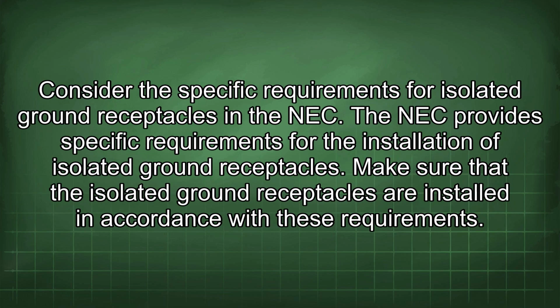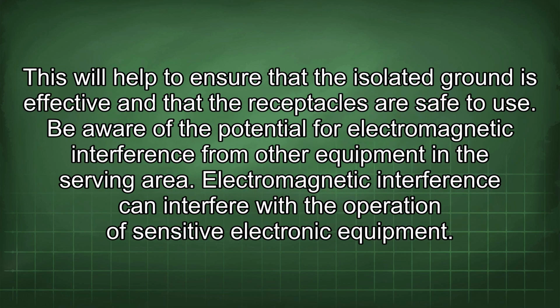Consider the specific requirements for isolated ground receptacles in the NEC. The NEC provides specific requirements for the installation of isolated ground receptacles. Make sure that the isolated ground receptacles are installed in accordance with these requirements. This will help to ensure that the isolated ground is effective and that the receptacles are safe to use.